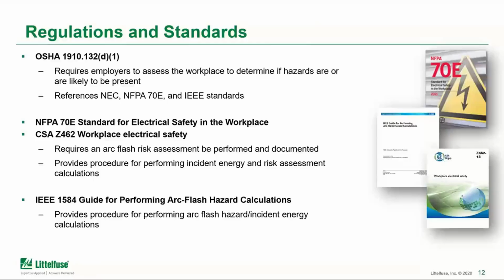So when you look at how the standards and regulations tie into this, OSHA 1910 is where it gives the mandate or the requirement to employers to provide that assessment. So that clause is where the requirement is given to do that arc flash hazard analysis if there are hazards likely to be present. The OSHA text doesn't describe exactly how the calculation should be done, but it references the other standards that are put together to address that. So it references NEC, the electrical code, as well as NFPA 70E and IEEE.